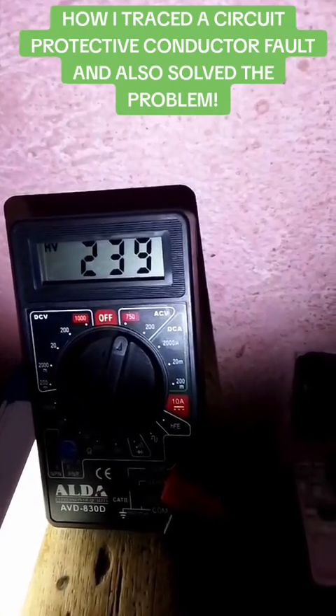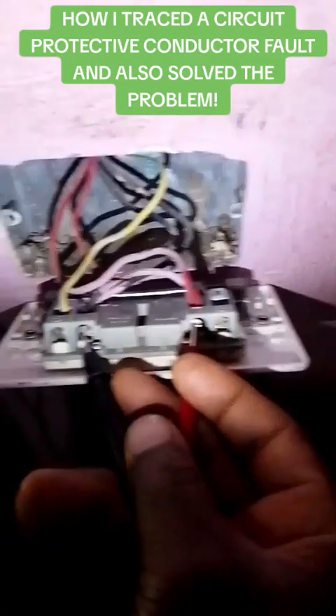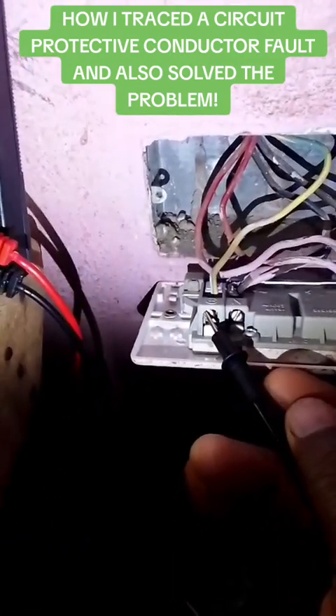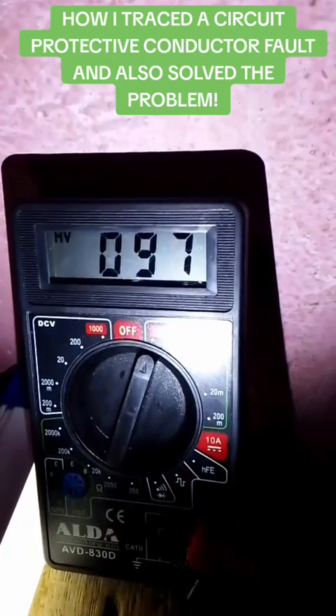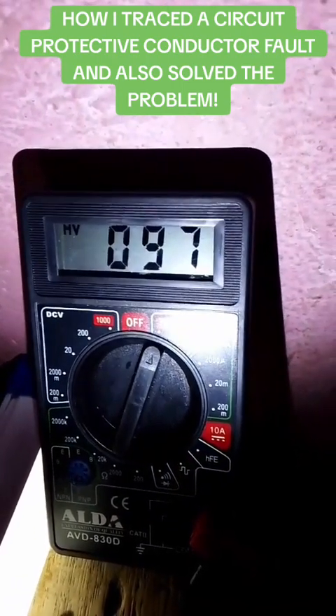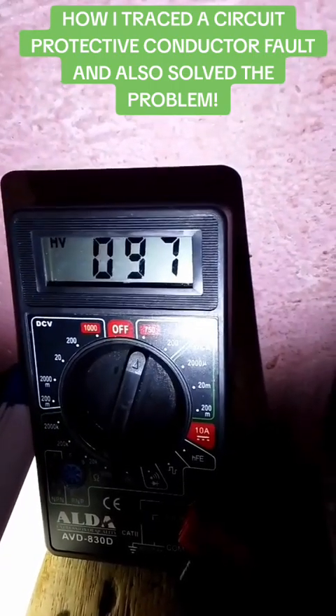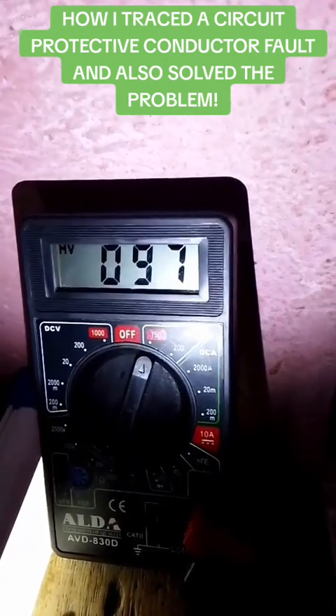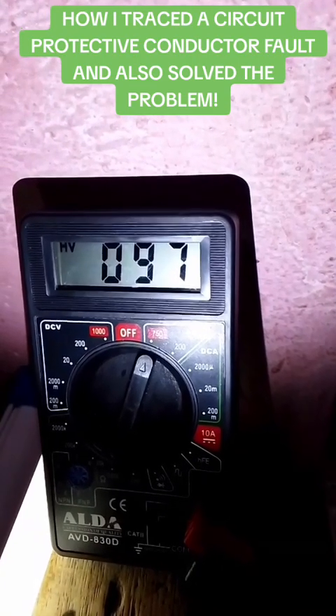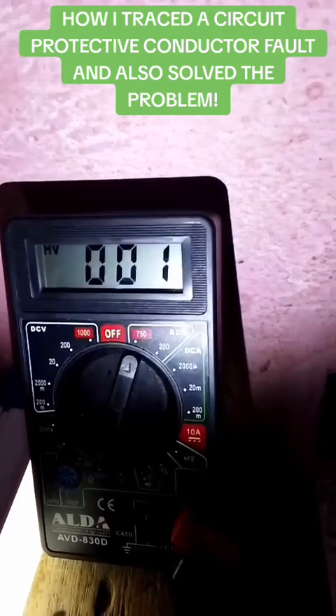So let's check voltage between live and earth. So live and earth, we are seeing 0.97, which is less than 1 volt. That means there's a problem with the earth. So we'll go to the main switch and see what is the problem with the earth.